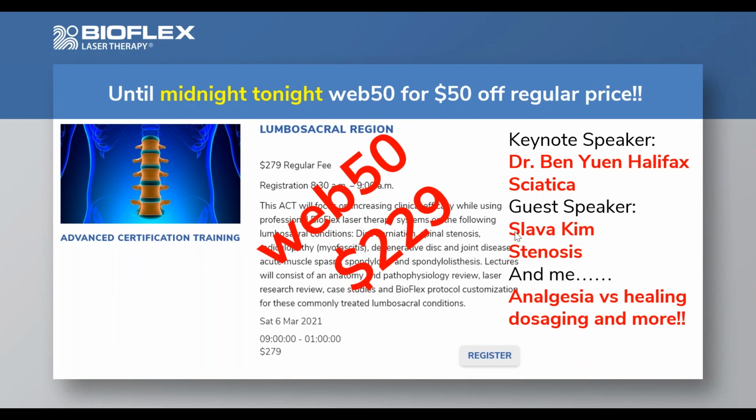A question from Evelyn. Hi, Evelyn. A colleague in Ottawa advised that a patient with plates after fracture says that they feel heat during treatment, but it was uncomfortable. Yeah, I don't know how to comment on that. We've treated many people with hardware. The equipment does warm up in its natural state because of electronics, especially the arrays, which do feel warm. So that might be the issue. But there's no way that this light from the LEDs or a class 3B laser has enough energy to heat up metal. It's impossible.